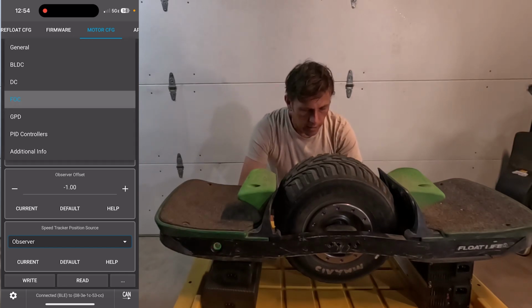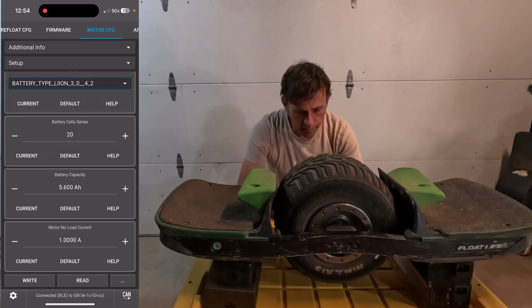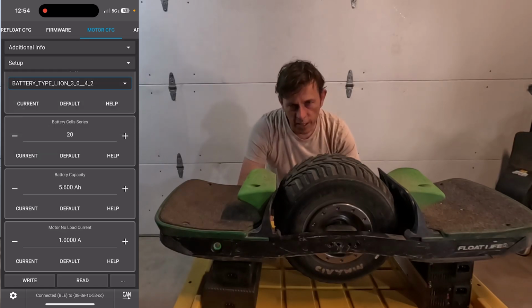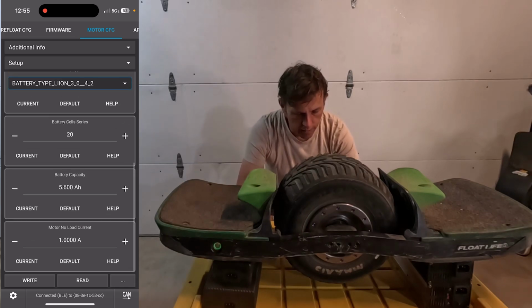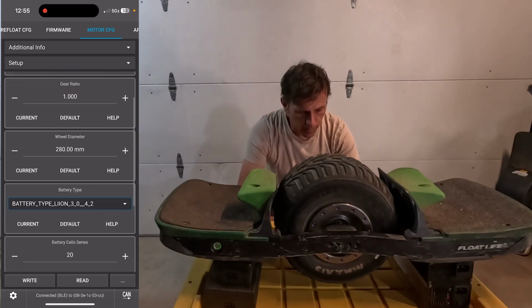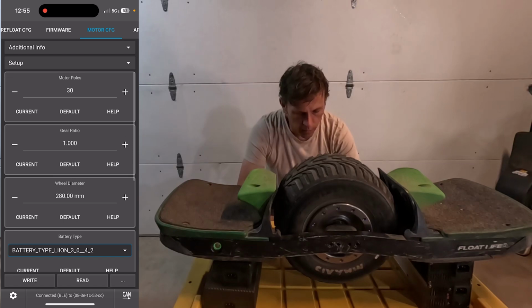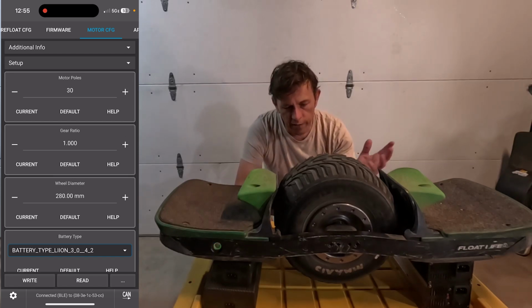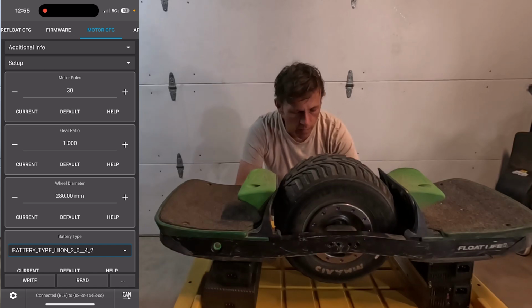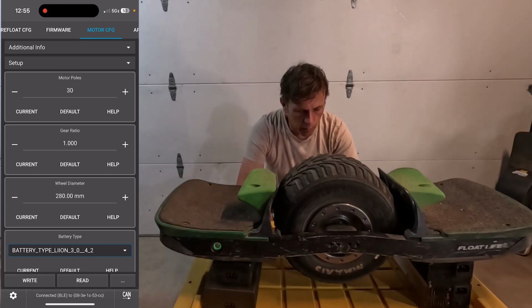All right, and the only other thing to note is additional info. If your speed isn't reading correctly, this is the area where you want to make changes. Up here we got the motor poles, that needs to be 30, gear ratio, this was that direct drive in the Wizard, it needs to be 1.0, and then here is the wheel diameter.